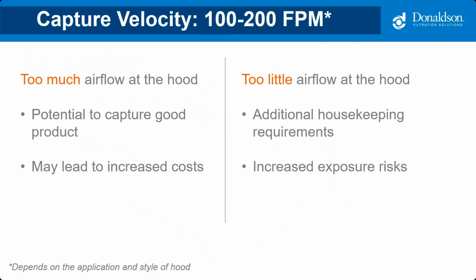So whether you're designing hoods or relying on machine design, we want to avoid airflow extremes. Too much airflow at the hood or pickup may mean you're picking up good product rather than just nuisance dust. And since more energy is required to move that airflow, it could lead to higher than expected operational costs. On the other hand, insufficient airflow at the hood could require additional housekeeping measures to be implemented, and depending on the dust, may lead to an increased risk of exposure.